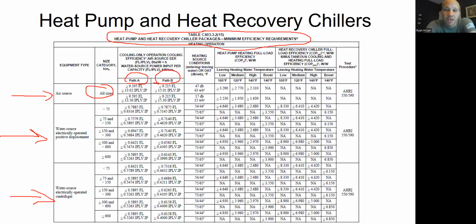And the reason we have path A and path B is because some applications need chillers that are very good at part load, meaning that they have all these different weather conditions going on, and you want to be able to be efficient when it's 95 degrees out, 80 degrees out, 70 degrees out, etc. Other chillers need to be more efficient at full load because maybe they're being used for a process application, or maybe you have like 6 chillers going in the building and you don't need to ramp each one up and down because they're small relative to the whole building, and you're going to turn them on fully one by one. So you don't care how efficient each chiller is at part load because you're only going to put the chiller either on or off. You're either putting 100 tons on or you're putting 100 tons off. So full load becomes more important.